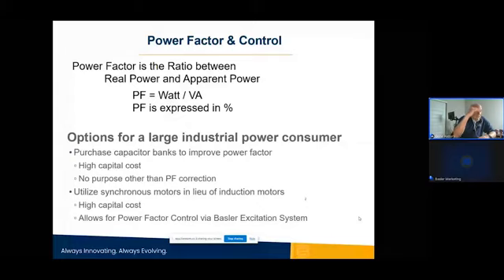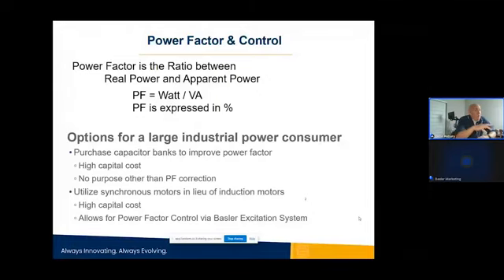And even though your supply voltage may dip, we built these excitation systems where they have forcing involved. Most of the time you think of forcing as something that happens with the generator. When you see a transient on a generator, you want to force the field to get that back to steady state voltage. But in a motor, it gives you the ability that if that line drops out, let's say you have a 150% forcing capability on a synchronous motor, that will tell you your line voltage can drop by 50% and you could still maintain the process. So that forcing level gives you that advantage in a synchronous motor that, you know, a DC power supply cannot.